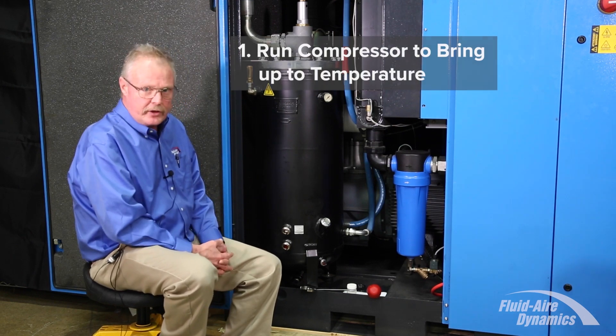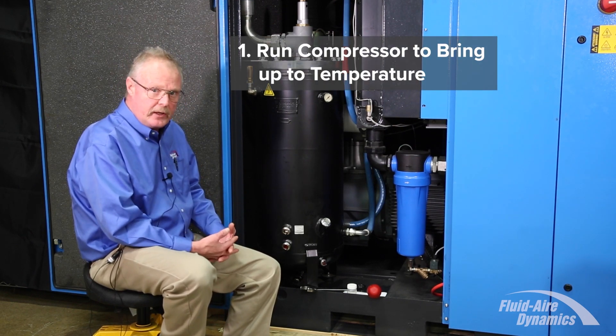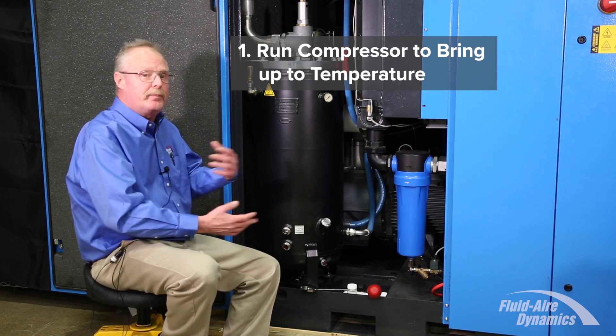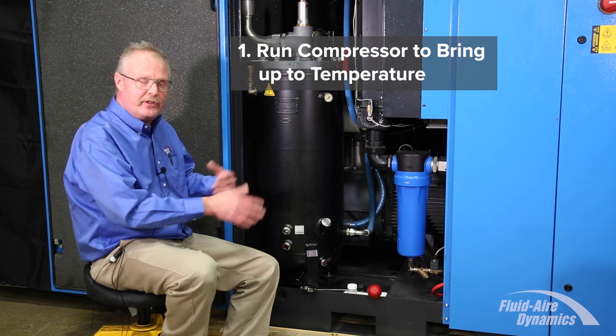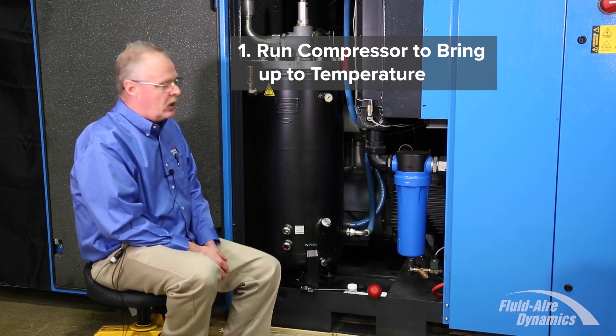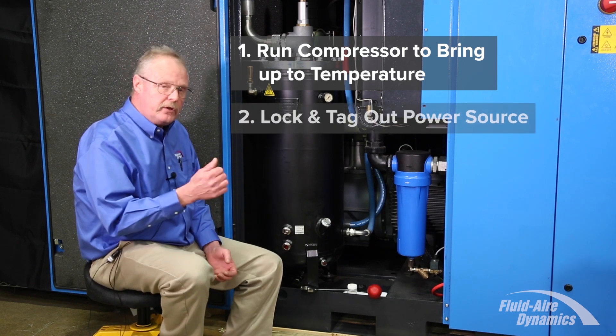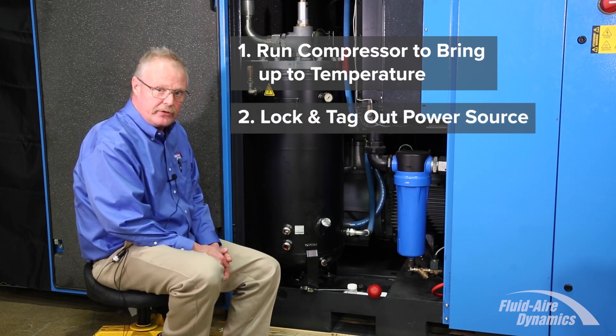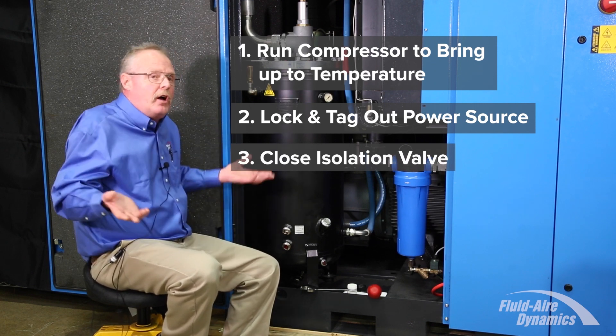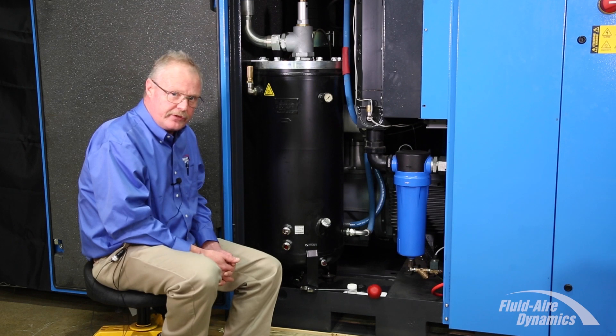Initially, run your compressor for a few minutes and bring it up to temperature. Once you've brought the oil up to temperature, that just helps mix all the particulates that may be inside the system in the oil so you'll get a true oil sample. Once that's completed, you want to lock and tag out your power source and close your isolation valve on the package, and release all the stored energy in the system.